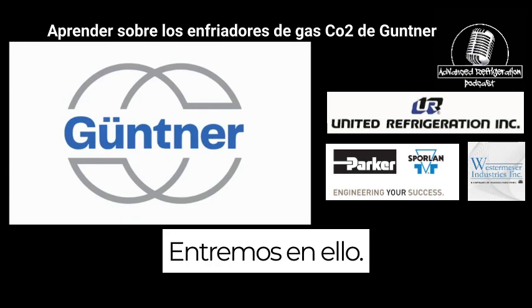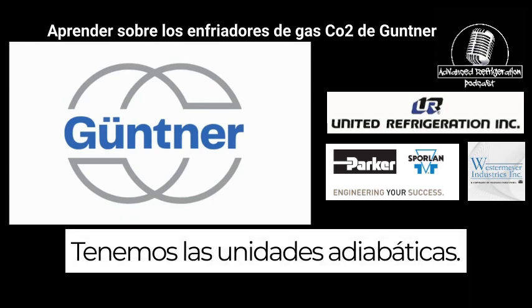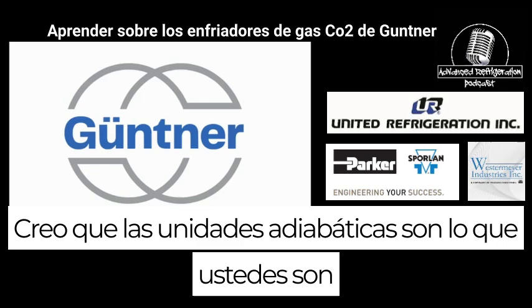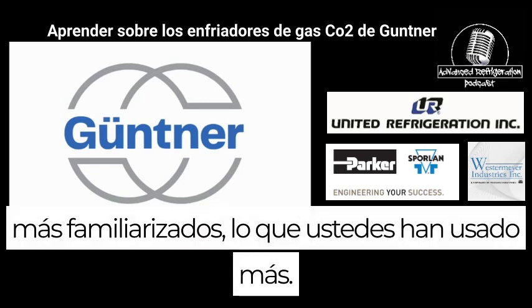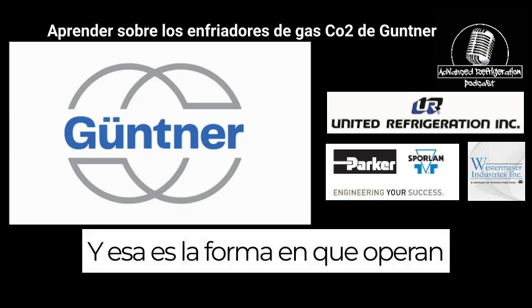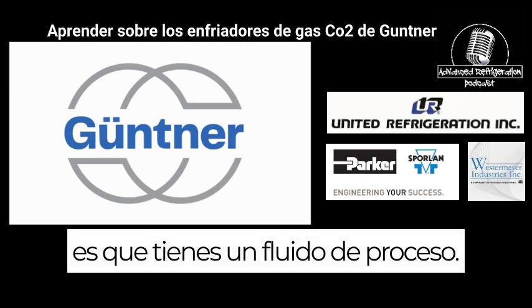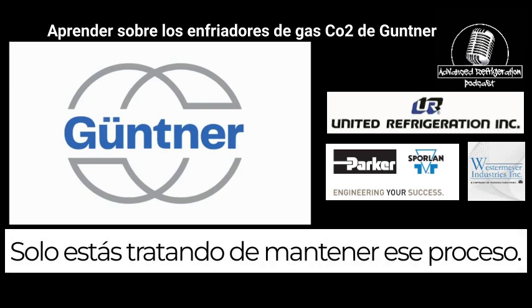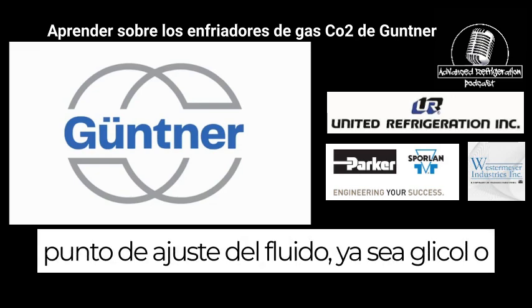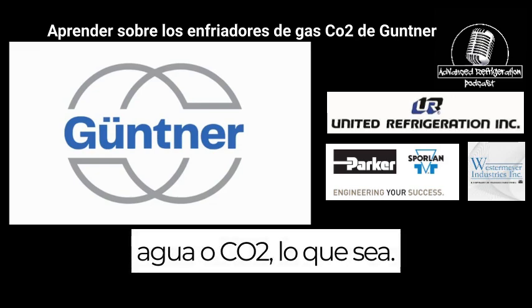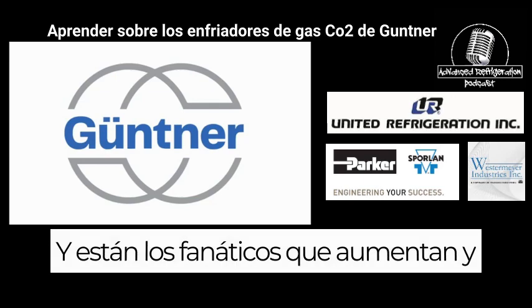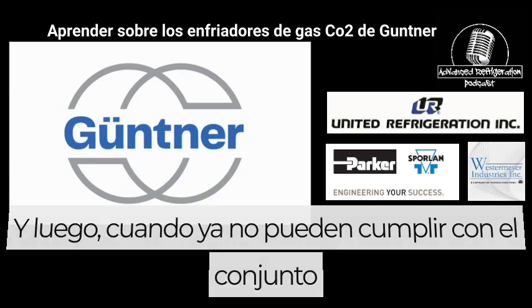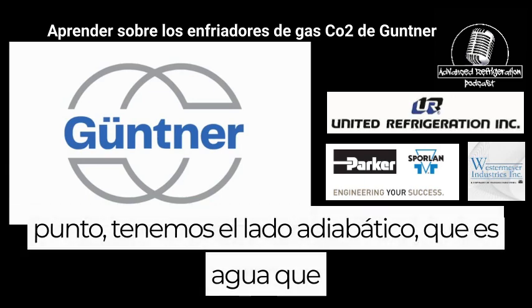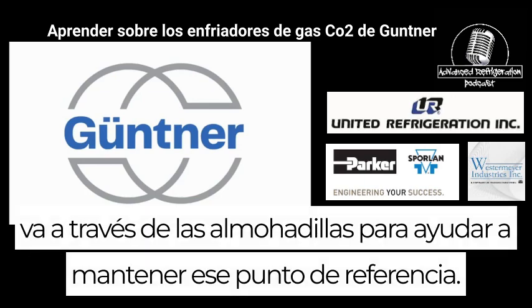Let's get into it. We have dry coolers and we have the adiabatic units. I think the adiabatic units are what you guys are most familiar with and have used the most. The way those operate is you have a process fluid, whether it's glycol or water or CO2, and you're trying to maintain its set point. The fans ramp up and ramp down to maintain the set point. And when they can no longer meet the set point, we have the adiabatic side, which is water that goes across the pads to help maintain that set point.